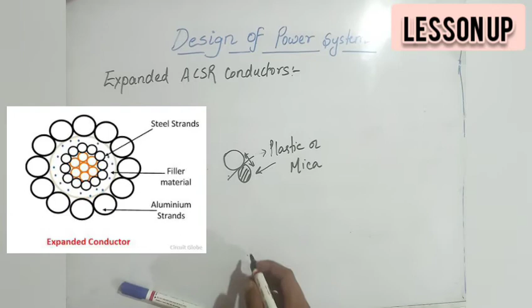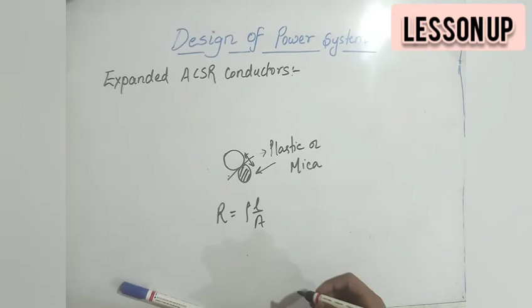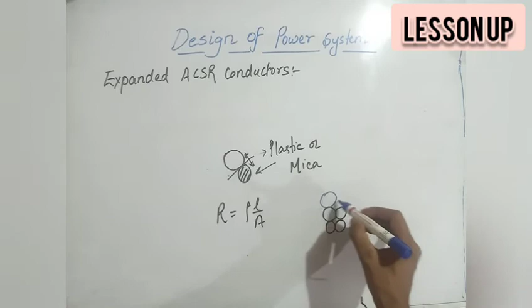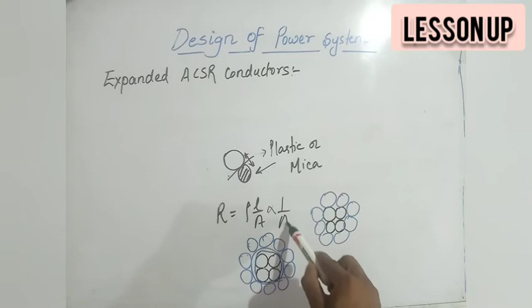With this insulation tape, the effective cross-sectional area increases and thereby resistance decreases, because as we know resistance is rho L by A. In composite conductor we have seen that the steel strand is in the center portion and aluminum strands are kept at the outer surface. So in expanded ACSR, we are providing insulation tape between aluminum strand and steel strand, so that they will not share any electrical properties. But due to this, the cross-sectional area will increase, and we all know that resistance is inversely proportional to cross-sectional area. So as the cross-sectional area increases, resistance will decrease.